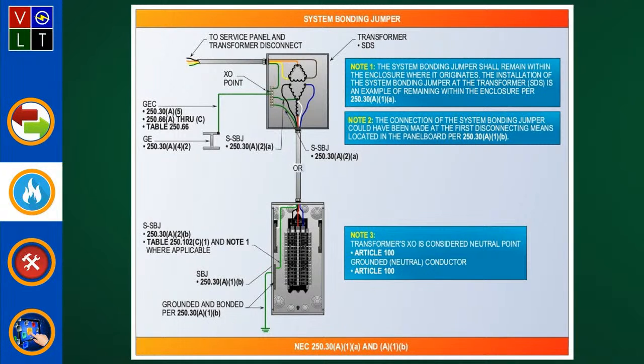Okay. Now, if I turn around and let's say I'm going to parallel at this point, and let's say I've got a 3-phase 4-wire service, and let's say I have 4 600 kcmil THW copper conductors per phase, what size system bonding jumper would be required to bond and ground that separately derived system at that point? Well, what you would do, I'm just kidding, you would go to step 1. And we said if you're over 1100 kcmil, well, we want to know what the kcmil is here. So I would just take the 600 kcmil times 4. That's pretty easy. That's going to give you 2400 kcmil.